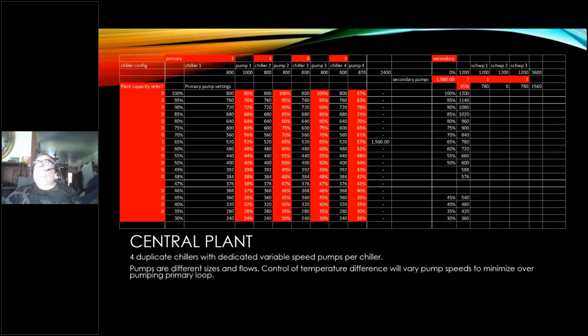So what we ended up doing is printing out a chart using our affinity laws and the pump curves in order to operate on. And in this case, the plant decides where it needs to operate. Let's say it's 65%. It makes a determination, okay, I need 3 pumps, but each one of the pumps, according to which pump I'm running, you set at different speeds in order to maintain the right flow through the chillers. But I need my pump curves to tell me which one of these is going to operate. So I've got one running at 52%. I've got another one running at 65%, and I've got a third pump running at 57%. So those would go in to maintain the right flow through the plant, okay?